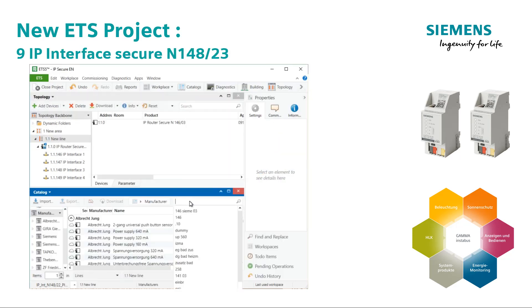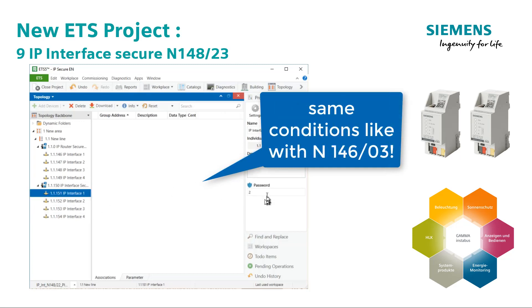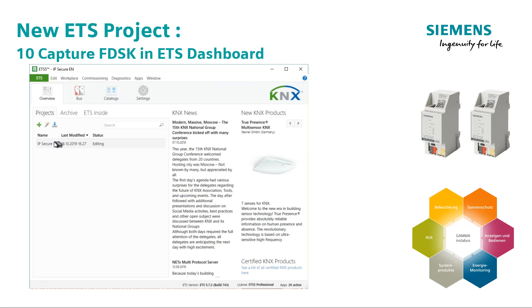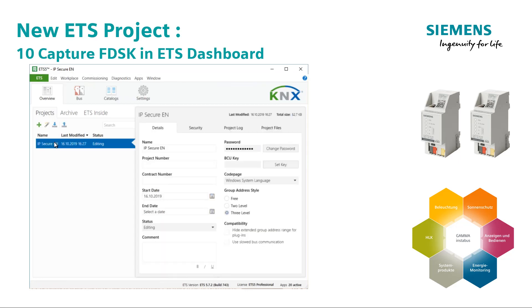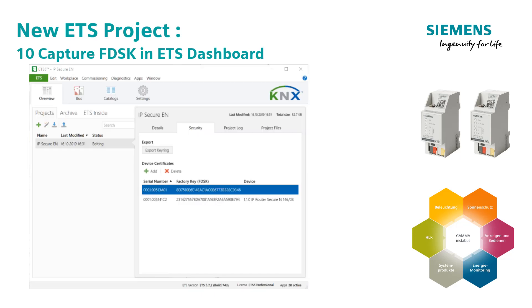Step 9: For the IP interface secure, the same rules apply as for the IP router secure, as you can see in the animation. Step 10: Capture the FDSK in the ETS dashboard. All project-related FDSKs can be found by opening the project settings. All device keys already registered for the project are stored in the Security tab, where further keys can also be entered, for example for the IP interface inserted earlier.